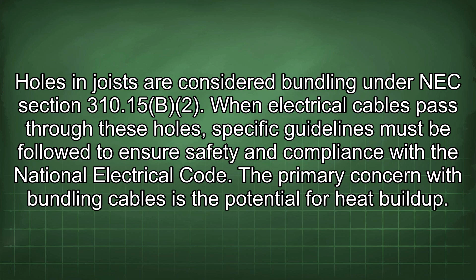Holes in joists are considered bundling under NEC section 310.15(B)(2). When electrical cables pass through these holes, specific guidelines must be followed to ensure safety and compliance with the National Electrical Code. The primary concern with bundling cables is the potential for heat buildup. When multiple cables are grouped together, the heat generated by each cable can accumulate, leading to higher operating temperatures.